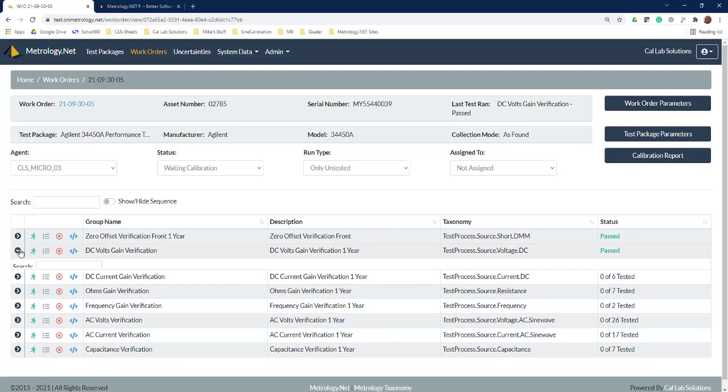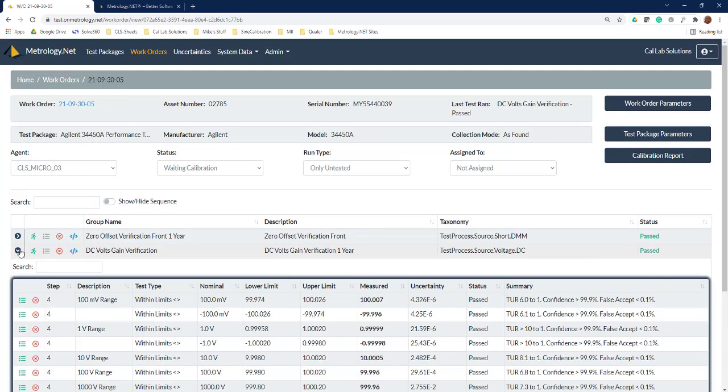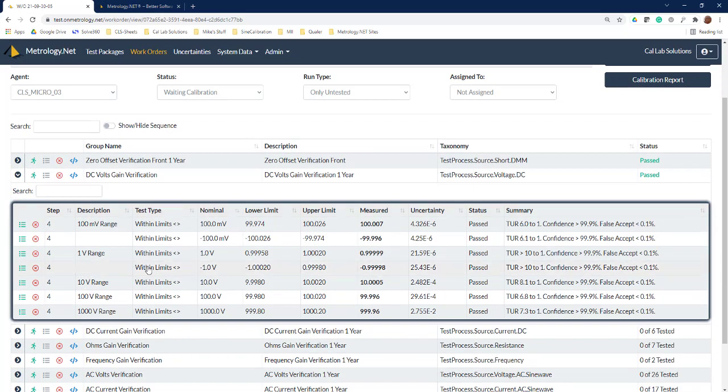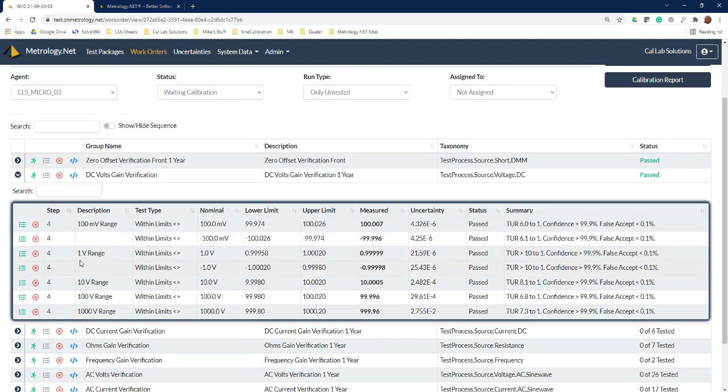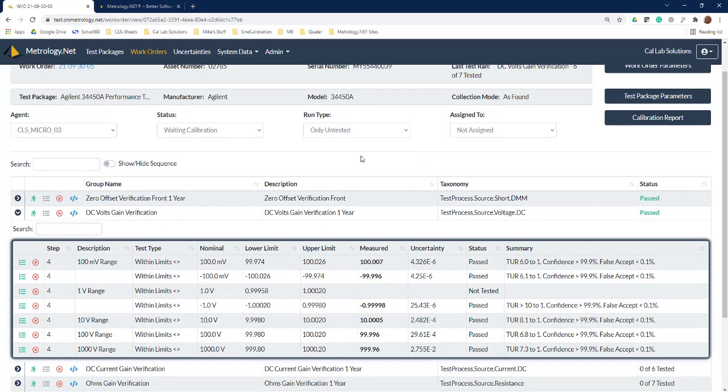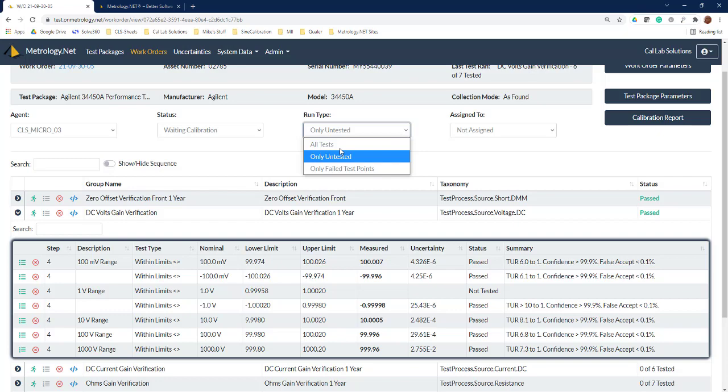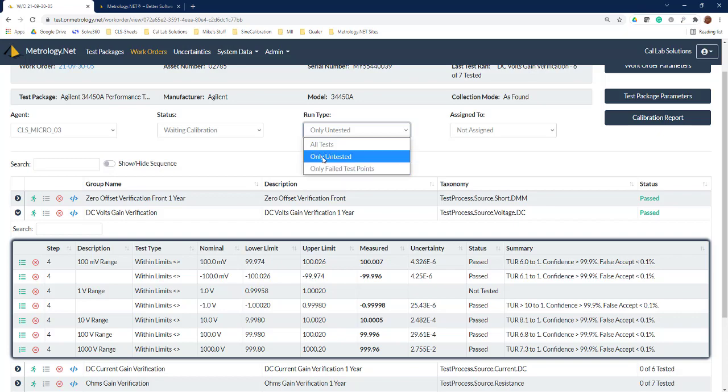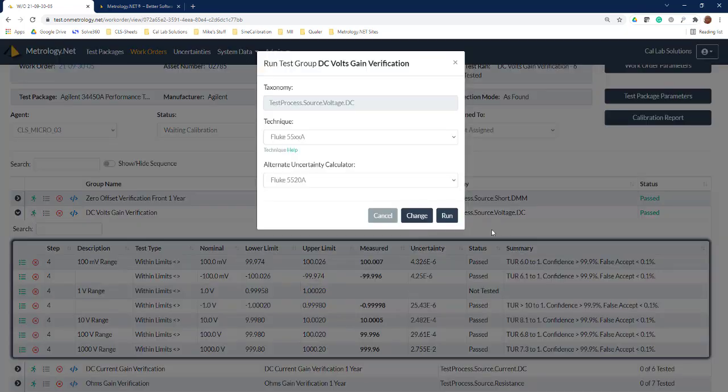Now expand this out—we should be done. So we've passed this calibration. One of the things we believe is that we want to let the technician be in charge of the calibration. So if there's a data point in here that he doesn't like, say this one volt range, we'll go ahead and delete this one volt range data point. And now up here we've got what we're going to run. You see how we're set to run only untested—we can choose all tests, untested, or failed data points. This allows us to go back in and double check connections or do something to figure out why something's not running. So we didn't like this one volt test point, we'll set it to only untested and we'll hit run this again.